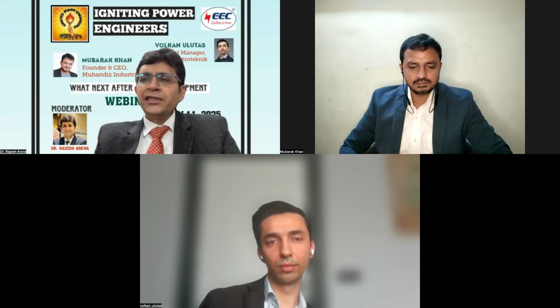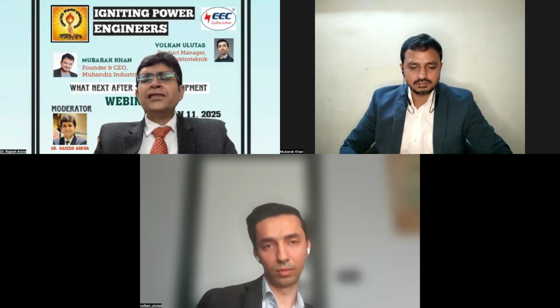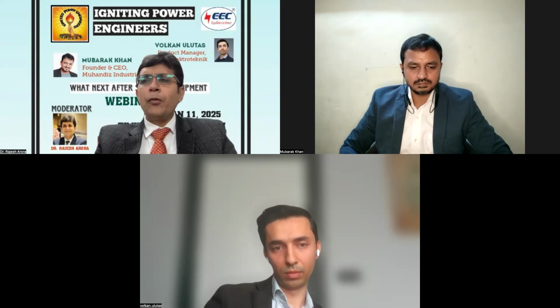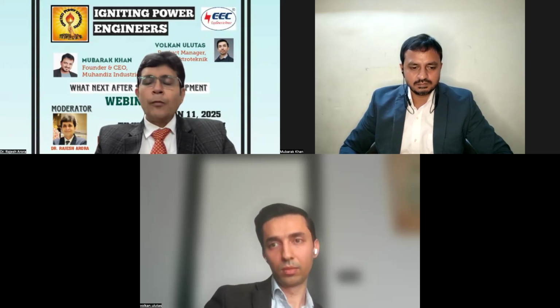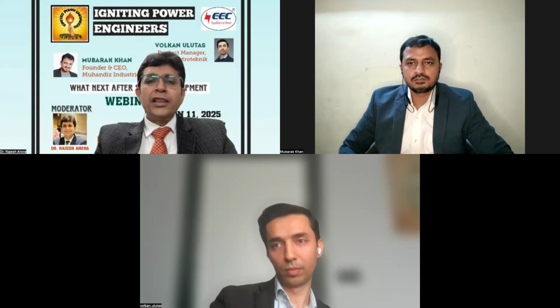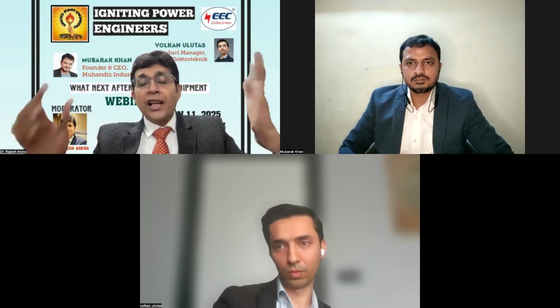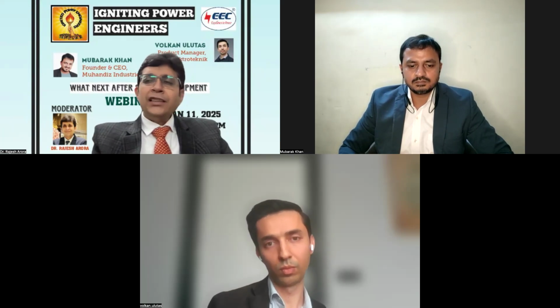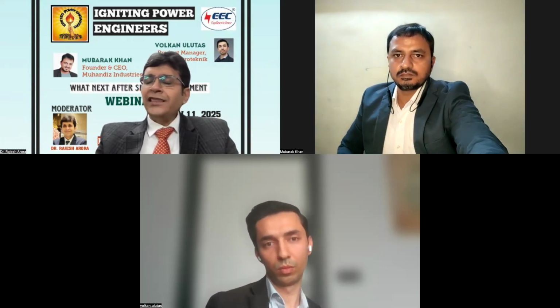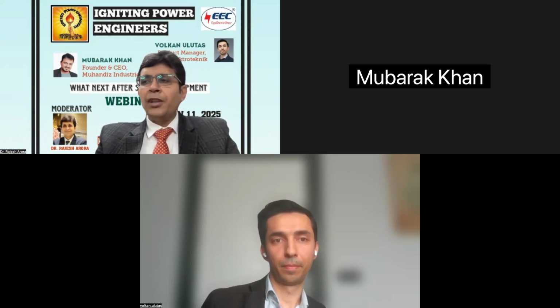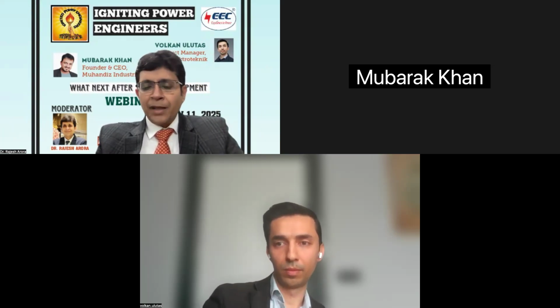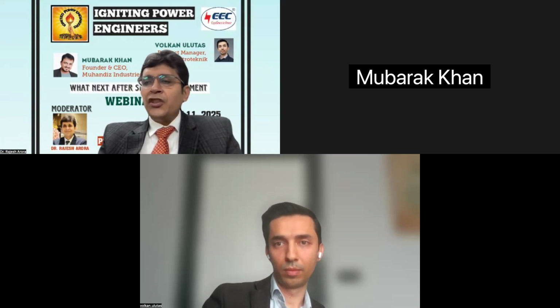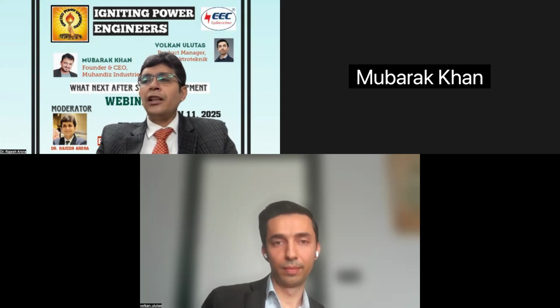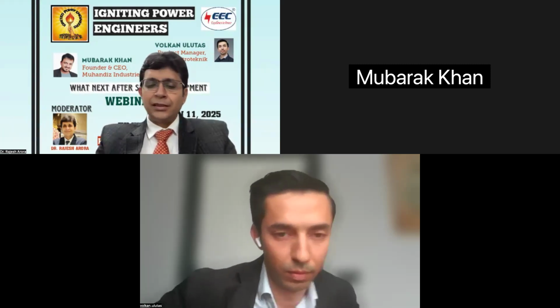When we say SF6 switchgear, SF6 (sulfur hexafluoride) gas is a highly potent greenhouse gas with a global warming potential 23,500 times higher than CO2. While SF6 is widely used as an arc quenching medium and insulating medium in all electrical switchgears like circuit breakers, GIS, and transformers, it offers several environmental and safety concerns that necessitate its phase out.